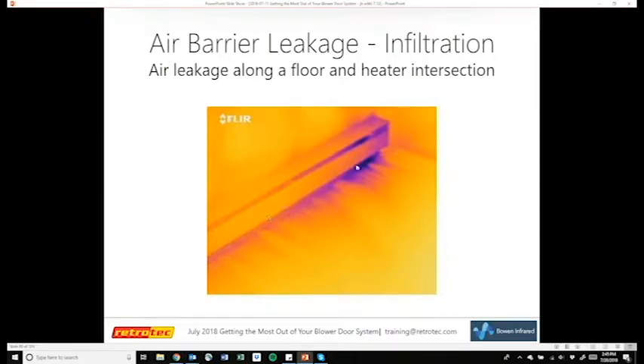A simple leak detection that is enhanced by a blower door is to give us that emphasis and that contrast and allow the thermal camera to pick it up as airflow across the surface. So here we can see airflow underneath this electric baseboard, and we can actually see that the majority of the leak is occurring over here, which would be indicative of a penetration behind that baseboard for the electrical wiring.